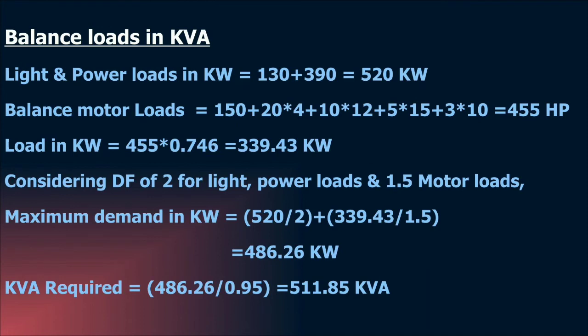Now we can calculate the kVA for the balance loads. Light and power loads, as seen earlier, will be coming to 520 kilowatt, and the balance motor loads other than the 200 HP motor will be coming to 455 HP, that is 339.43 kilowatt. Considering a diversity factor of 2 for the lighting and power loads and 1.5 for the motor loads, the maximum demand in kilowatt will be 520 divided by 2 plus 339.43 divided by 1.5, which is the same as 486.26 kilowatt. Considering a power factor of 0.95, the kVA required will be 511.85 kVA.